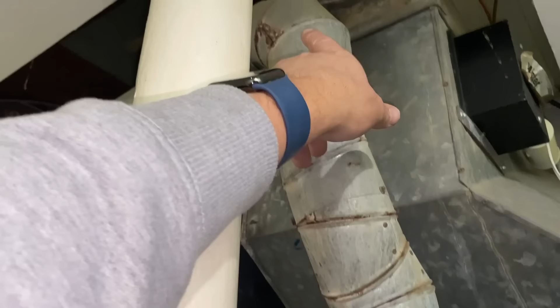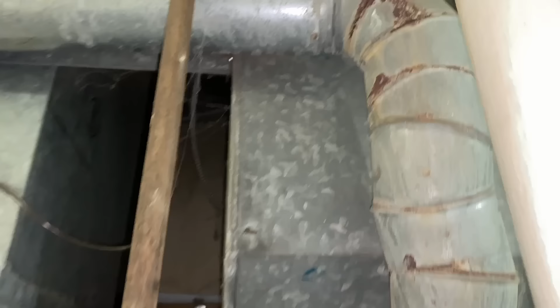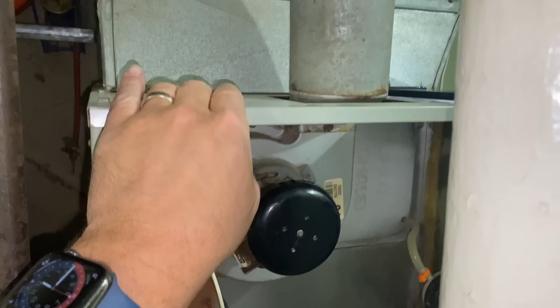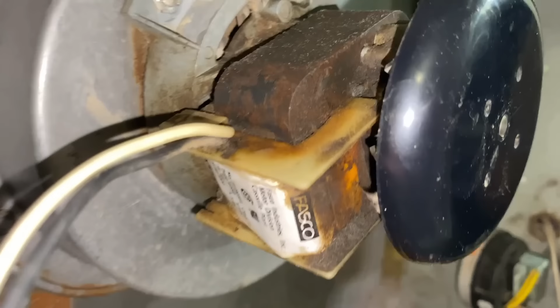You see all this rust on here? That's caused by condensation or condensate of the exhaust gas, which has some vaporized condensate, which is not water, but it looks like water, but it's not, and it is starting to leak there. So you have water damage there. That's what that's caused by. You have some burning marks, charred marks on your inducer assembly.